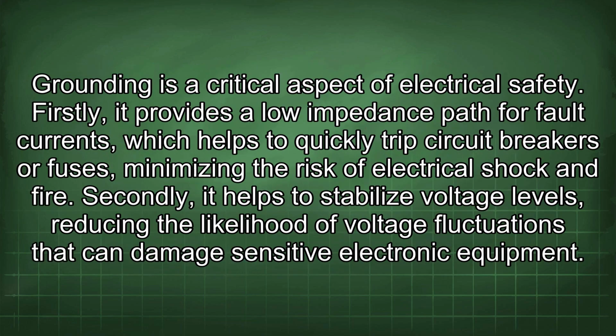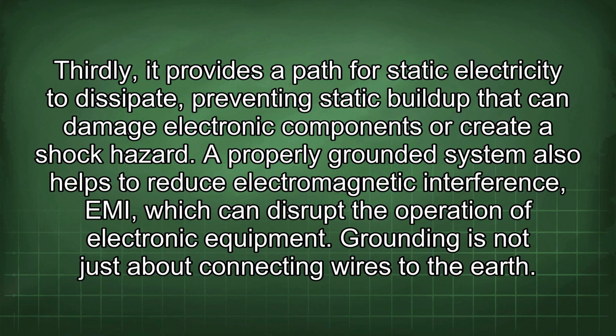Grounding is a critical aspect of electrical safety. Firstly, it provides a low impedance path for fault currents, which helps to quickly trip circuit breakers or fuses, minimizing the risk of electrical shock and fire. Secondly, it helps to stabilize voltage levels, reducing the likelihood of voltage fluctuations that can damage sensitive electronic equipment. Thirdly, it provides a path for static electricity to dissipate, preventing static buildup that can damage electronic components or create a shock hazard.